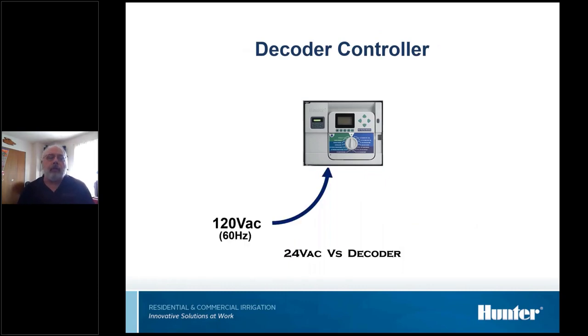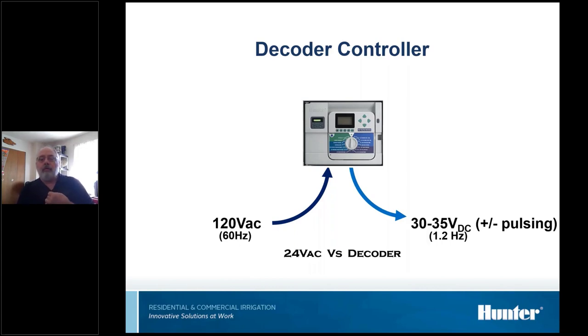On a decoder system, we still come in with the same thing, 120 volts, 60 hertz. But what we come out with is this pulsating voltage. It's actually about 35 volts, but there could be some variance depending on how far down the wire path it is. But it's at 1.2 hertz, pulsating DC voltage or a square wave, and standard test equipment does not know how to deal with this. If you ever hooked up a regular voltmeter to a two-wire system, the voltage bounces all over the place. It actually bounces back and forth between two general areas, and you can use that once you know what it should look like, but it's a little odd.